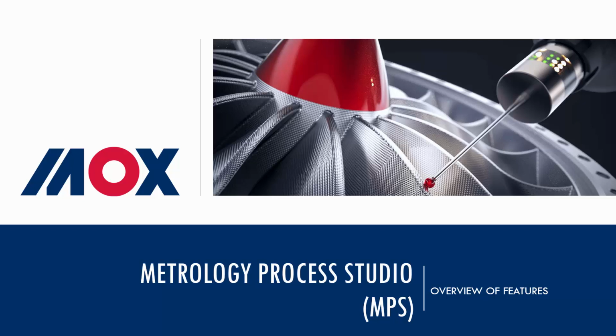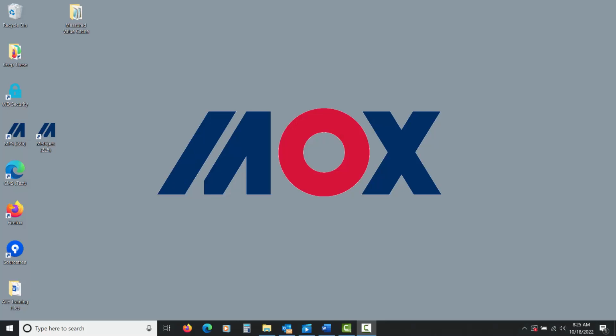MOX MPS uses a Microsoft SQL Server database to store its data. Optionally, you can also save these as files. There are two ways to launch MPS, either directly or if you're using MOX CMS, when you go to perform a calibration within MOX CMS, there's an option to have it launch MPS with the appropriate datasheet template and everything loaded, ready to perform the calibration.